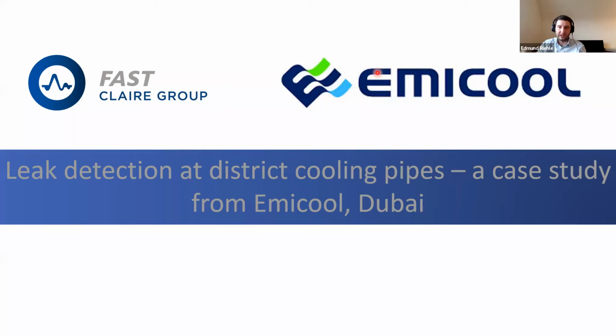And also you have additionally the insulation around the pipe, which makes it even more difficult to detect. Also with, for example, a tracer gas method, it will be very challenging because the gas will not escape through the insulation, but distribute inside the insulation. So we had to apply some other technologies there, and I will introduce you to this project and how we achieved good results even in these very difficult circumstances.